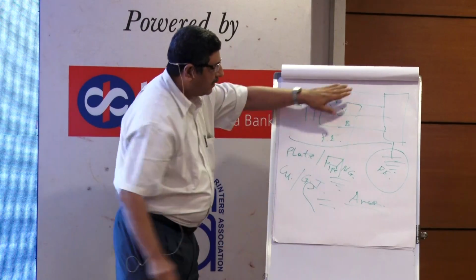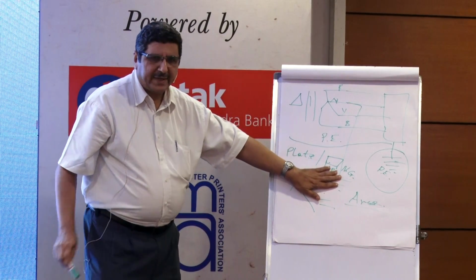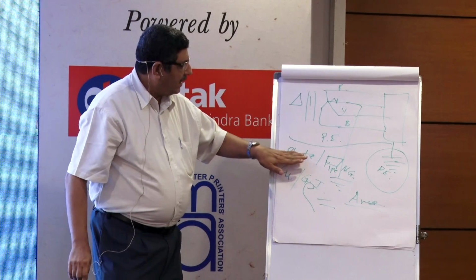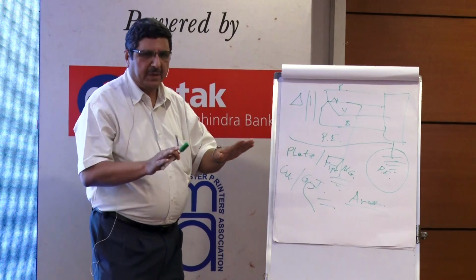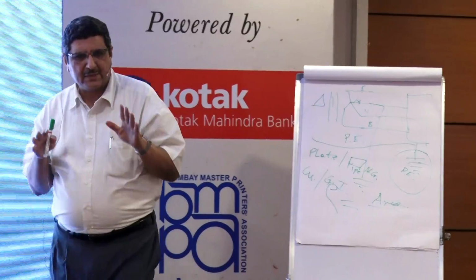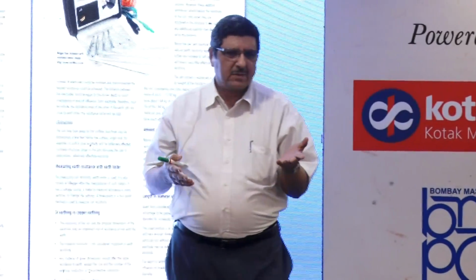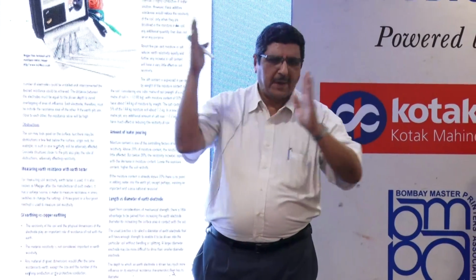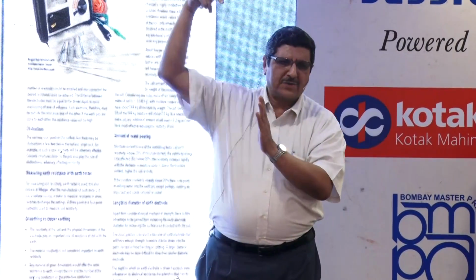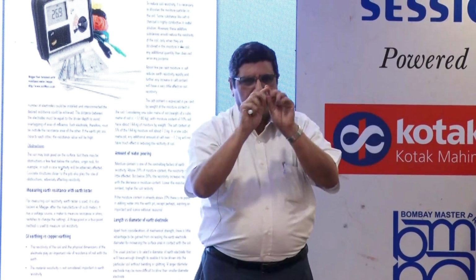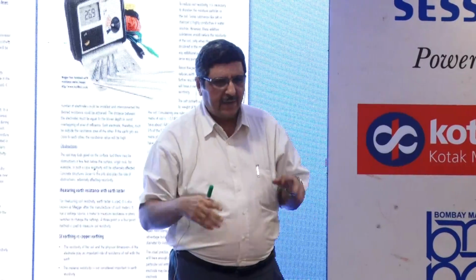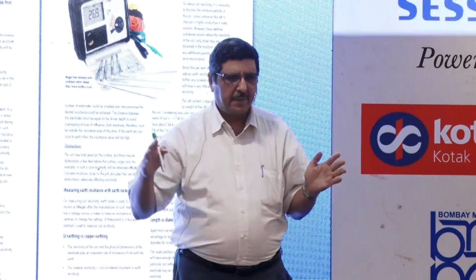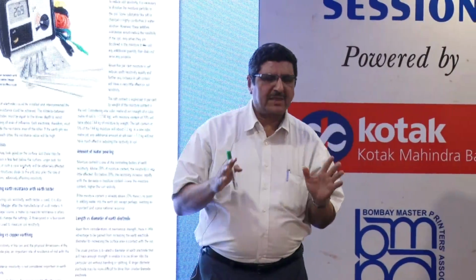For the neutral grounding where the transformer is fitted, copper is required, tin copper is required. So for that, either plate or pipe is acceptable. Now in my case, what I do? Plate costs 2,000 rupees. Take a pipe, take a plate, sandwich it, put a strip so you get a better area. If you open out the pipe, you get an area, and the plate gives you an area of 2 by 2 feet, 6 thick or 10 thick, galvanized plate.